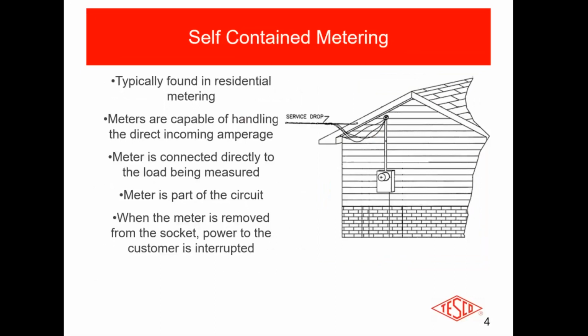Self-contained metering. Why is it important? Well, it's what most of our metering is. A little over 85% of most of our meters are 2S residential self-contained. There's other self-contained forms, Form 12 and 16 and a couple of others. These are typically found in residential metering, maybe some very small commercial industrial. The meters are sized and are capable of handling all of the incoming current. Which means what? It means that the meter is part of the circuit. If you take the meter out of the house, off the building, it kills the service.